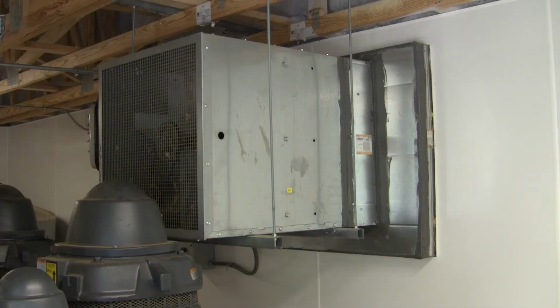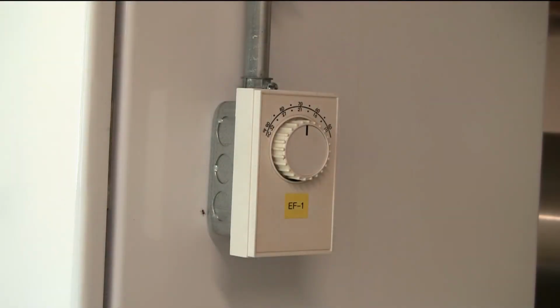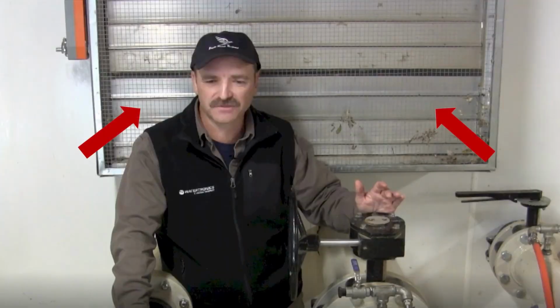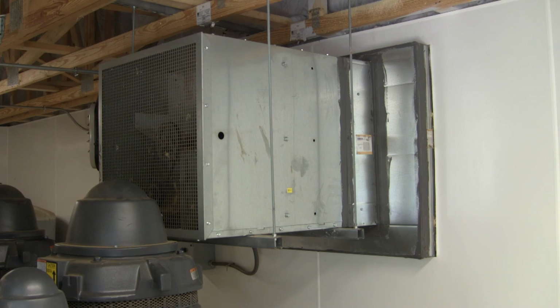And one of the other issues that we come across all the time is improper ventilation for the pump station. We come in, there's no fans at all, no ventilation at all. In this case, this is a properly sized ventilation system for the number of motors and pumps that are here. On the other end of the building, there's an automatic louver which opens and then allows the air to cross-ventilate through the station.